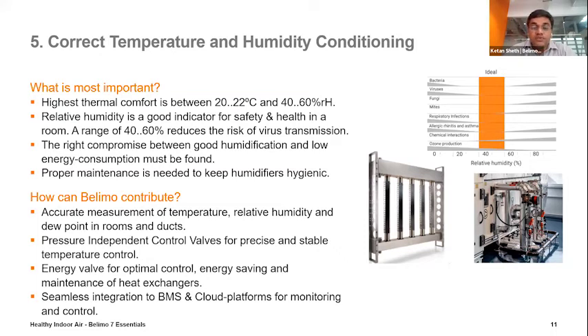How we contribute is, again, we always start with measurement, like an accurate measurement of temperature, relative humidity, and especially the dew points in the room and duct. Here we have an electronic pressure independent control valve for precise and stable temperature control. We have an energy valve, which is the next level of this electronic pressure independent valve, where we have three different types of control. One is an optimal control with the delta T manager, which also helps in energy saving, managing the delta T and maintenance of the heat exchangers, chillers, and especially the AHU coils.